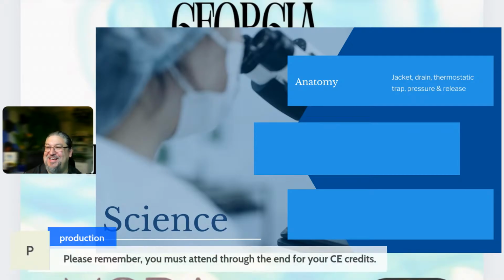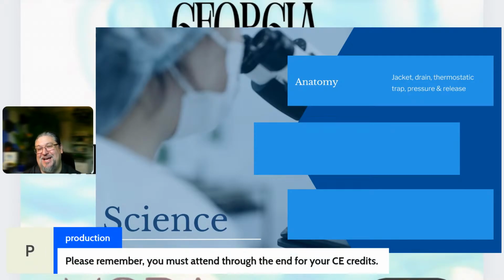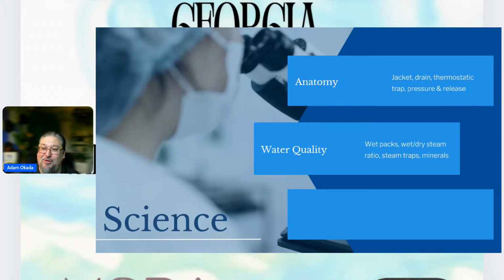So there's a lot of anatomy that we have to understand about how the sterilizer works, that the jacket fills with steam first, then it can go into the chamber and it's already kind of conditioned so that's not going to create condensation. There's a lot to go into that. We talked about water quality and how important that is, but in sterilization specifically, if you're having issues with wet packs, it is most likely going to be the wet to dry steam ratio that is thrown off. So I had this in one of my departments.